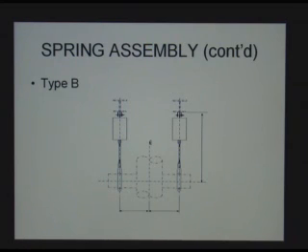And this assembly is used when you've got vessels. You've got a pipe coming along from the top, the column. You can pick up with the lugs here, two of them. If the load is 10,000 pounds, you use two of them, will be 5,000 pounds each. They are very effective and they last forever, believe it or not. They're just like the shock absorbers under your car. Or you see in the front of the engine underneath, the springs, basically, there's nothing in them except just a coil. In the casing, it's just coil in there.